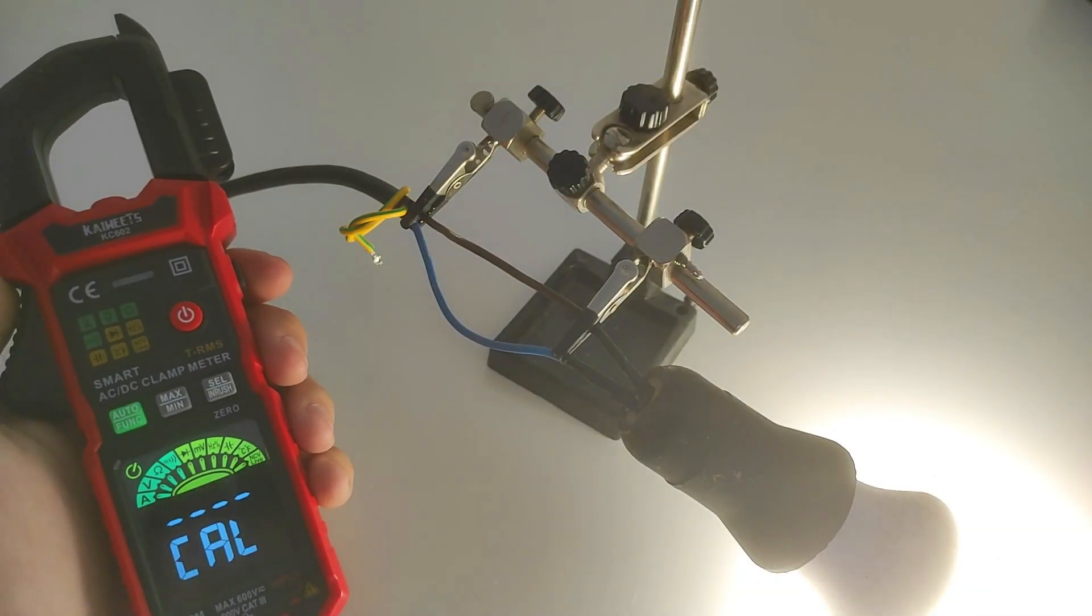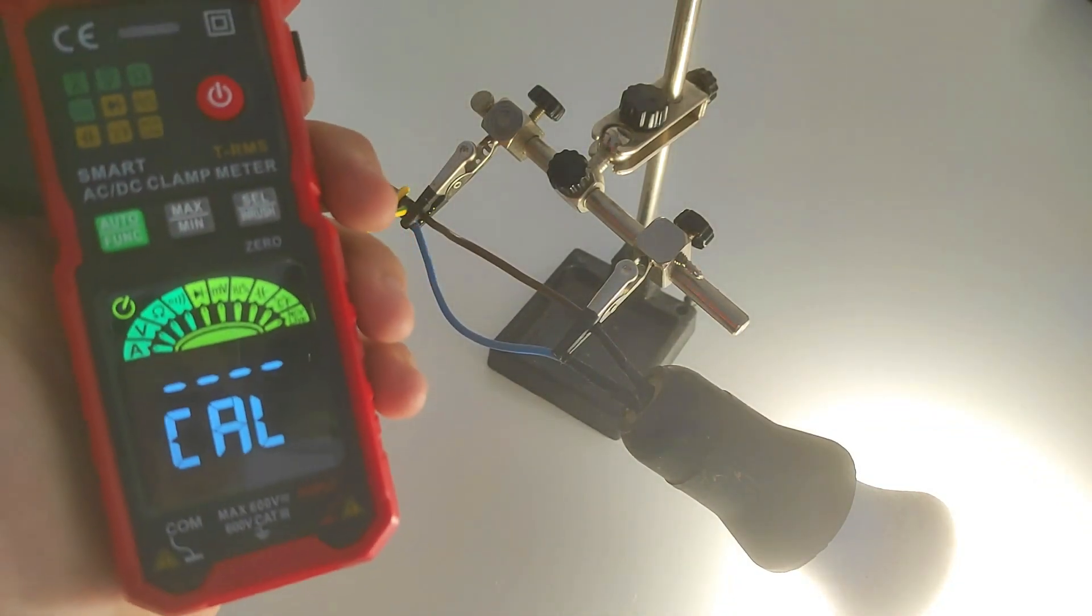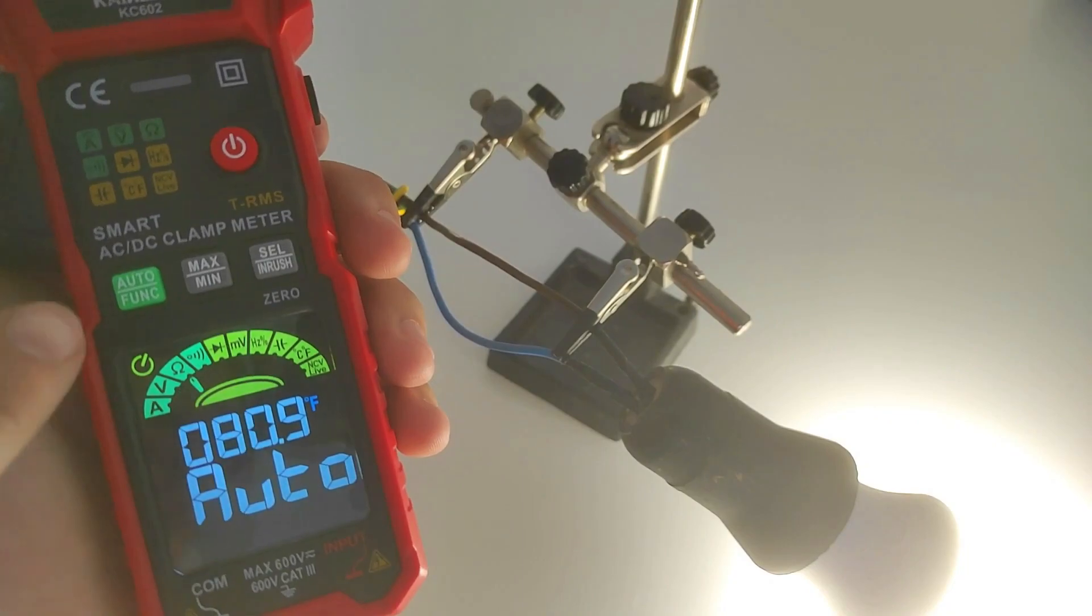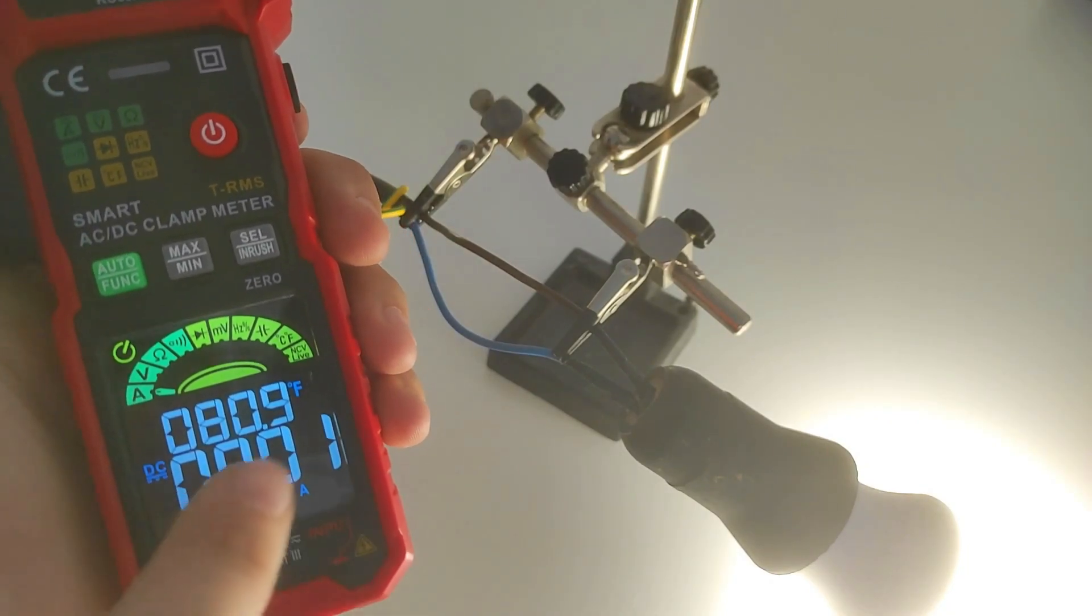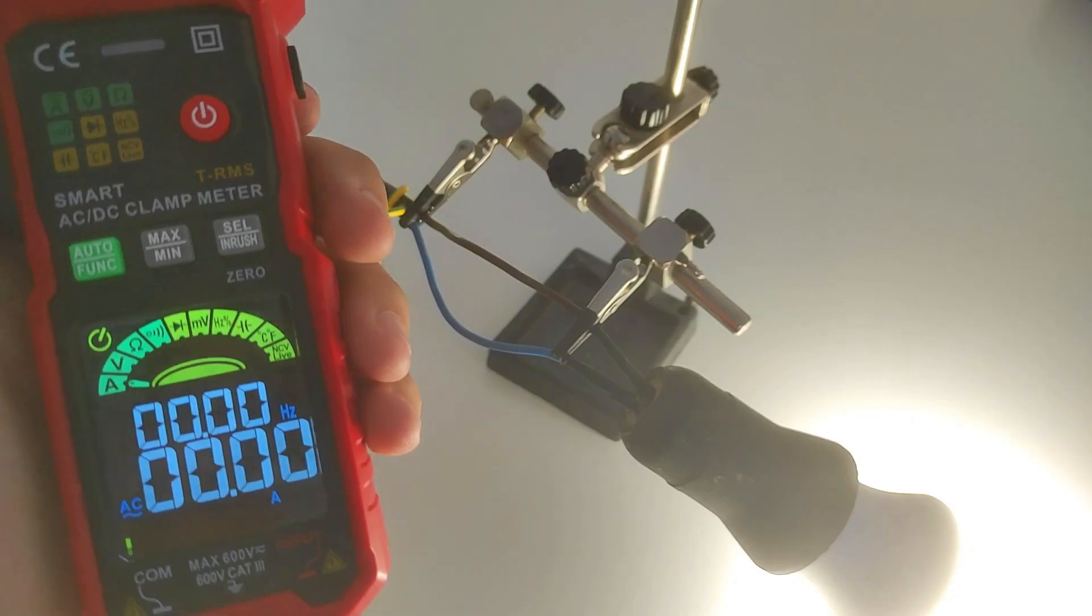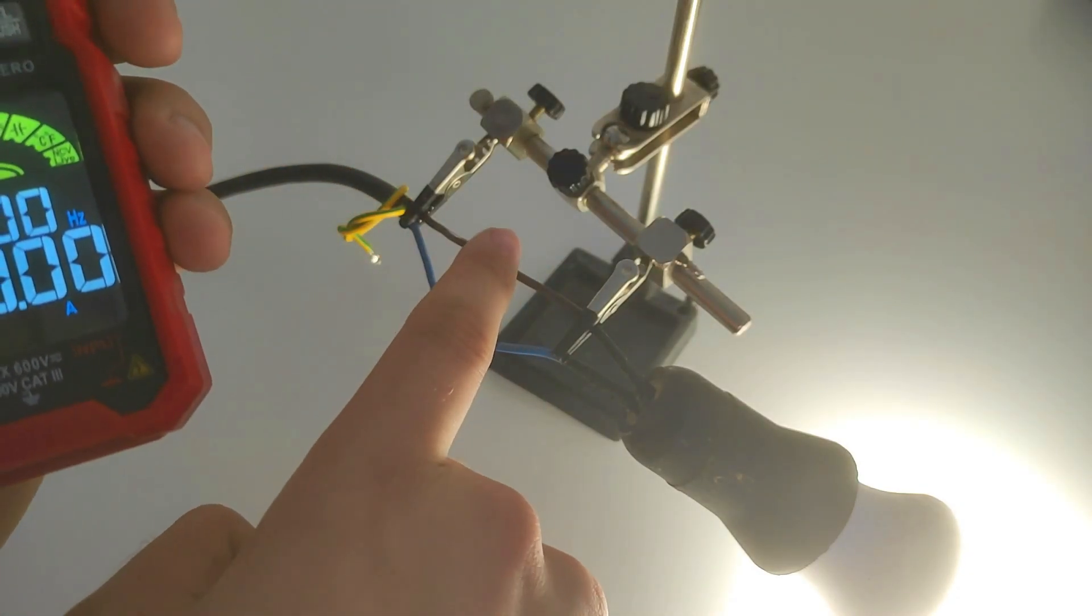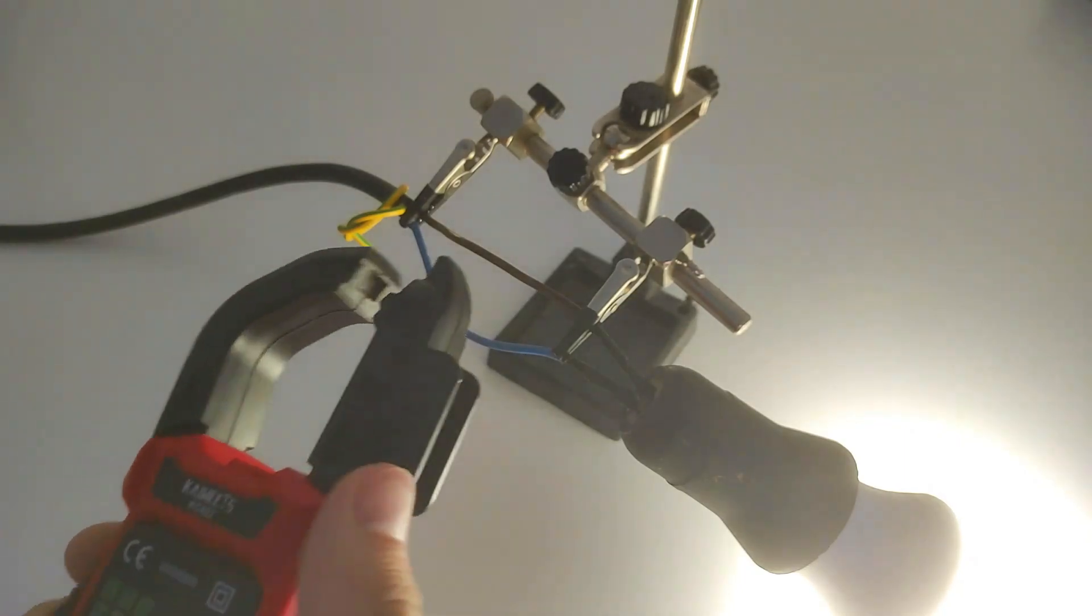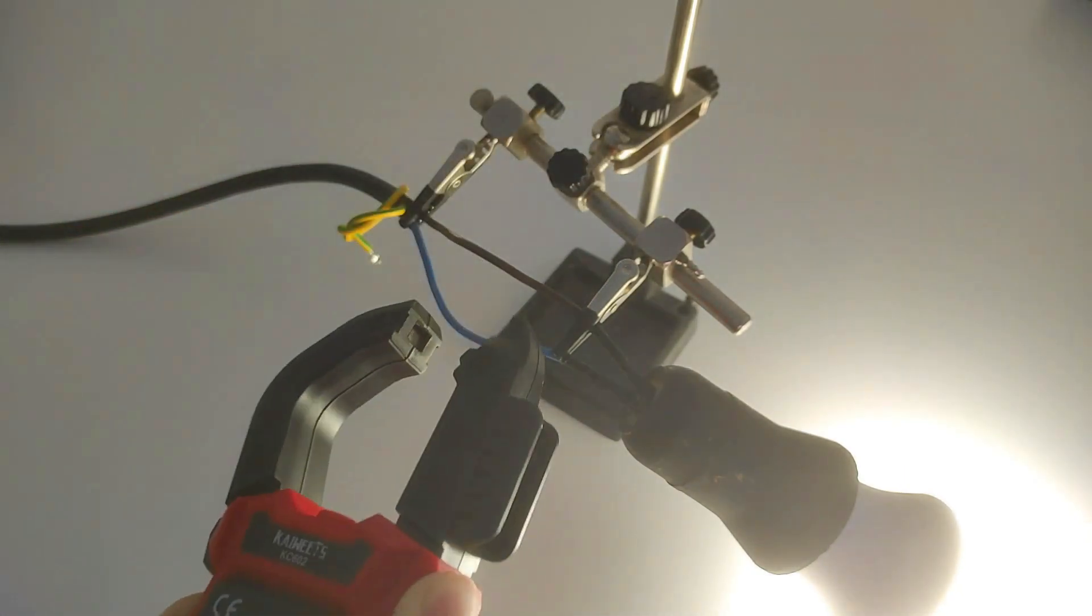The main function of the clamp meter is to measure current flow. This is done by first turning on the device, then selecting the A symbol, and choosing AC by clicking the Inrush button. Then you select the wire that conducts the current, namely the phase wire, and clamp it with the jaws.